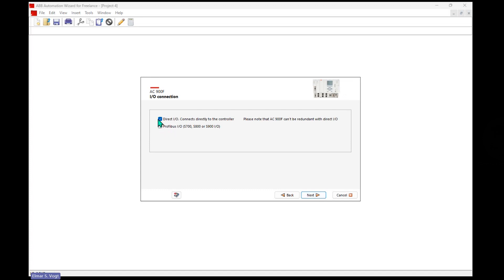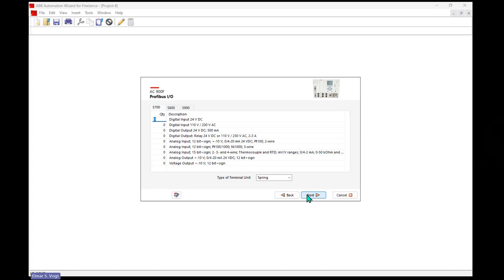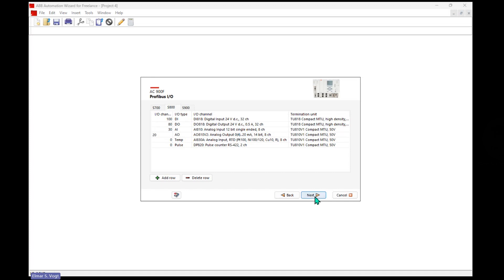So I specify what kind of I/Os I want. In my example, I don't go with direct I/Os, but I go with Profibus I/Os and with a redundant Profibus line. I specify some S800s in here. So yes, I want to go with 100 digital inputs and 80 digital outputs and 30 analog inputs and 20 analog outputs. Quite easy one.